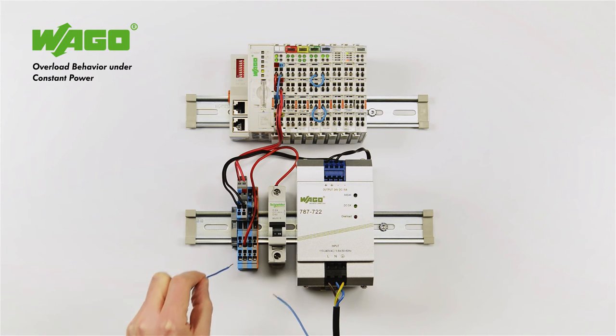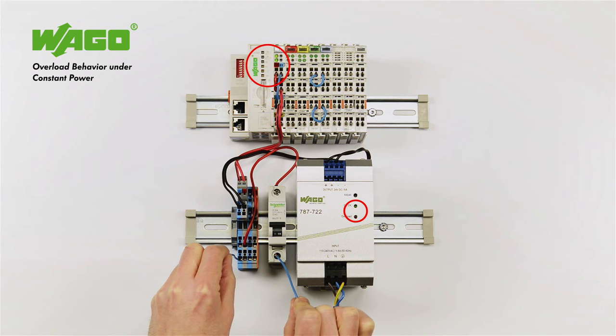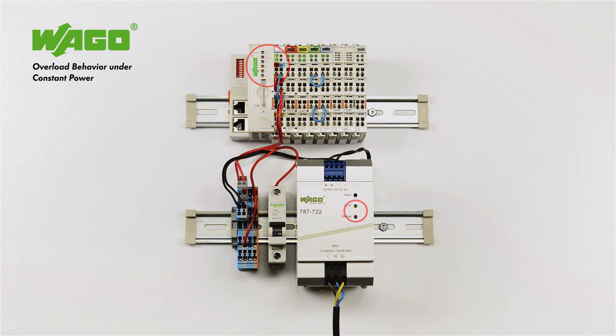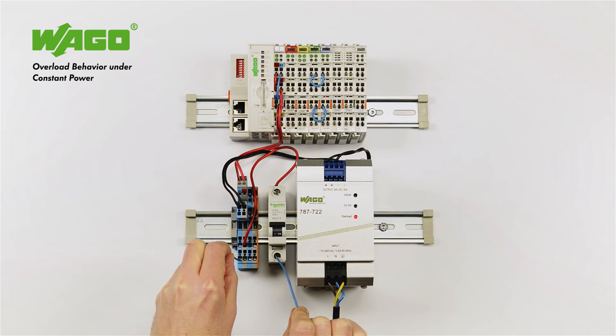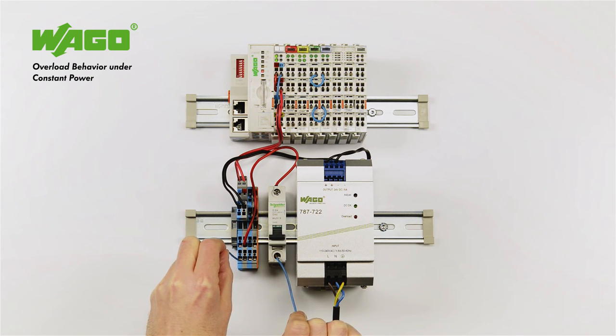The disadvantages with a short circuit are, however, similar to those found in hiccup mode. As the short circuit current is also limited in this case, the magnetic section of the fuse in the miniature circuit breaker cannot react. But the output of the power supply unit is not disabled here, meaning that the thermal section of the fuse will open the electrical circuit after an undefined time. A higher current is applied to the output circuit until this happens. This could result in a cable fire if thin conductors are being used. An electronic fuse can be better adapted for this and provides more reliable tripping.